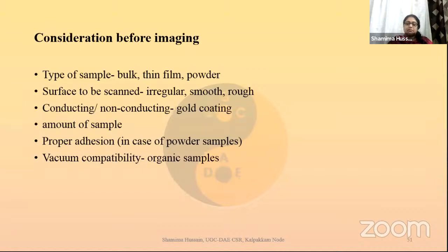Why is this regular surface required? Because if you have uneven height, you may have the chance of hitting the pole piece with your sample. In that case, it would be a very terrible kind of damage to the system. And also, the most important part is that you have to have a conducting surface. Now we are talking of electron microscopy where the probes are electrons. So it is very important that my sample surface is conducting. That means whatever electrons I'm shining on my sample, they need to have a path from the sample surface down to the ground. Otherwise, they will reside on the sample surface. They will give you some kind of surface charge effect, which is going to hamper all the features we see. So what do we do?